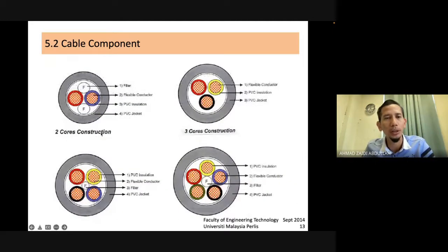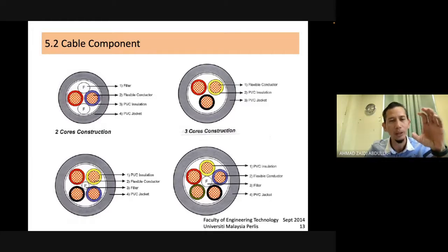Okay, and this is the sample. Let's say 2 core, you have an ordinary cable, like a normal plug cable, with live and neutral. 3 core, we have 3 cables, RYB, and then 4 core, RYB and neutral. The last one, as usual, has a PVC jacket, filler, conductor and insulator. The insulator just covers the phase conductor, and the filler is just paper, used to fill up the cable so that it fits and doesn't move around. That is the function of the filler.